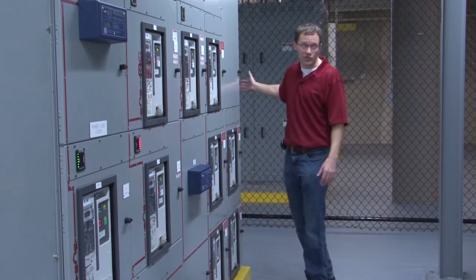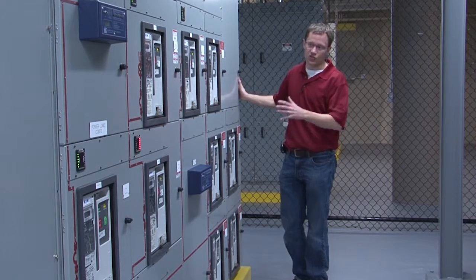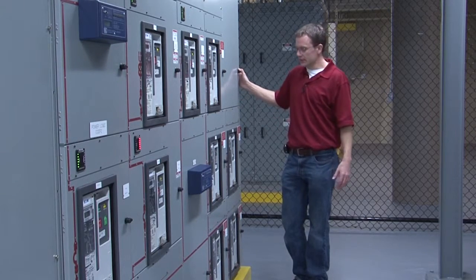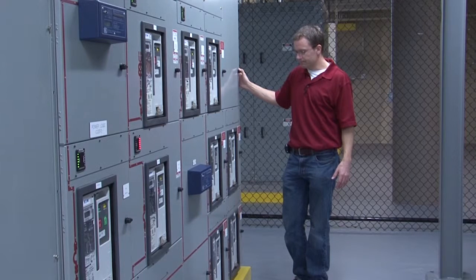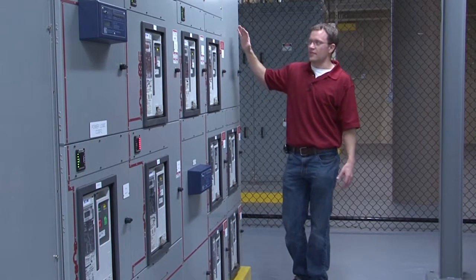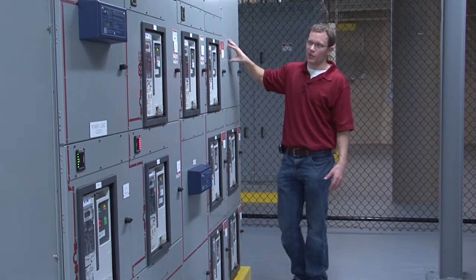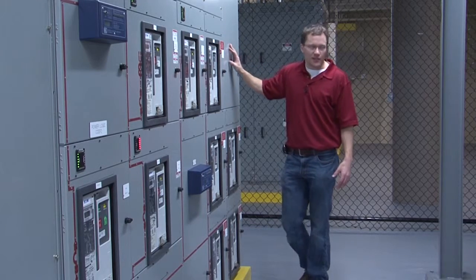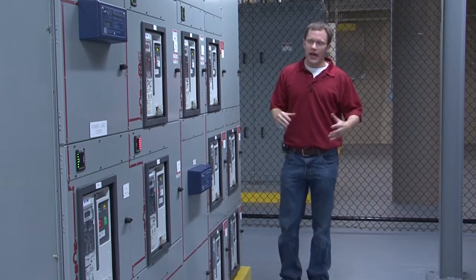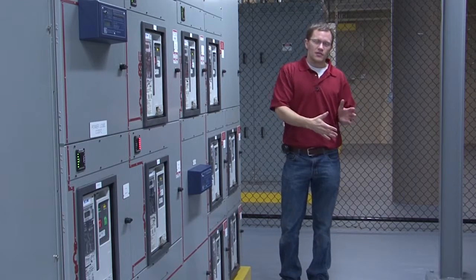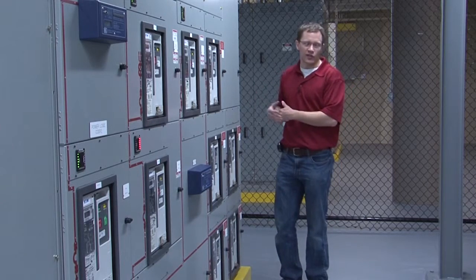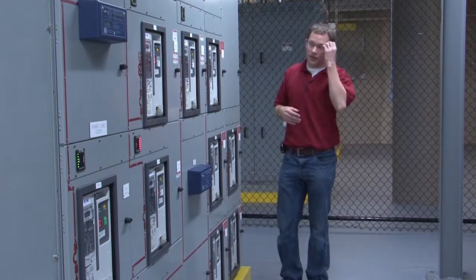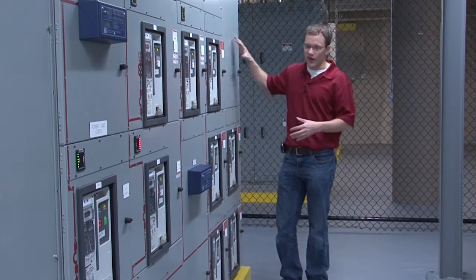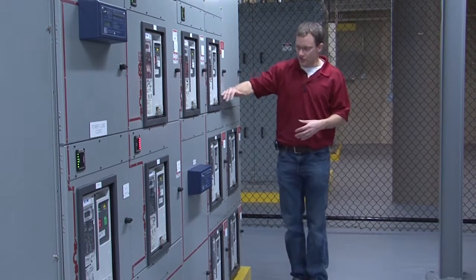Obviously there's no transformer associated with this. It's not really a substation, it's just a switchboard. So each UPS, there's five modules per system. It's different than the existing. The existing has a system cabinet and all the modules send power to it, and then it sends power out to the load. Here there is no system cabinet, so all the modules feed directly to the COD board through these 5 breakers.